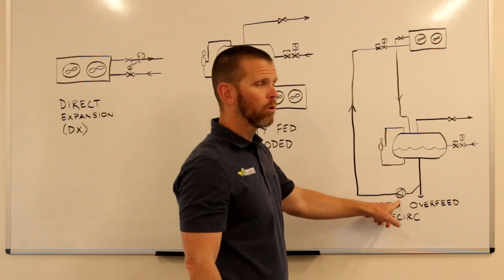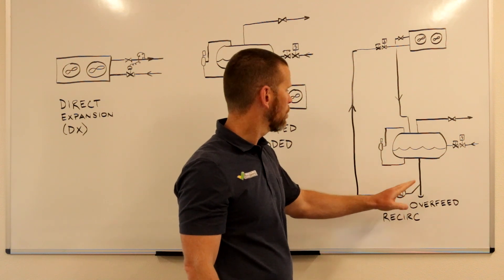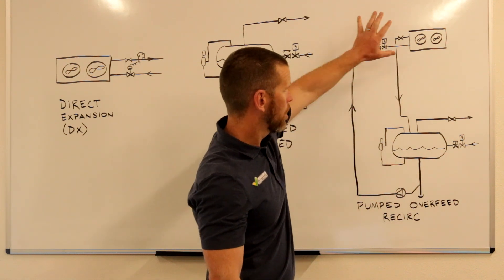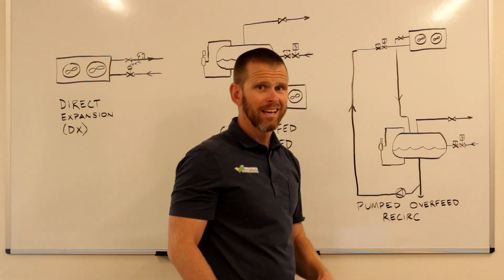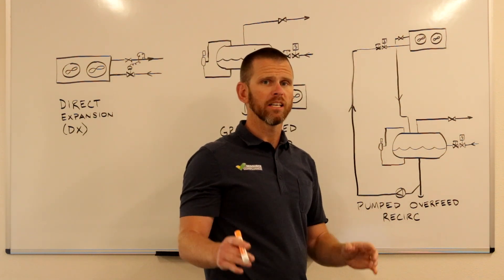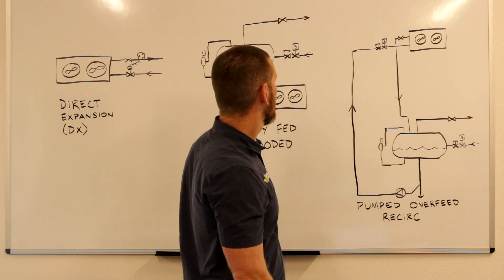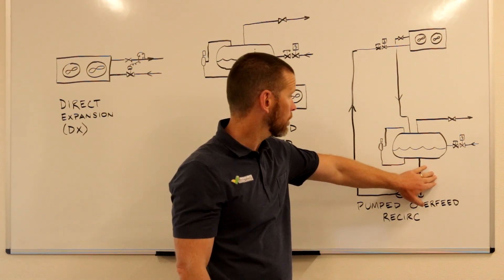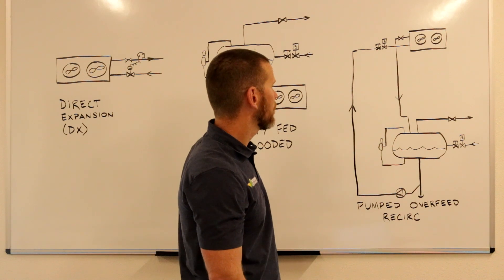instead now we will employ a pump that will move our low pressure liquid to the evaporator, which I've shown above the vessel in this case. And that evaporator can be a long distance away from where the pump is and the recirculator is for this pumped overfeed system.